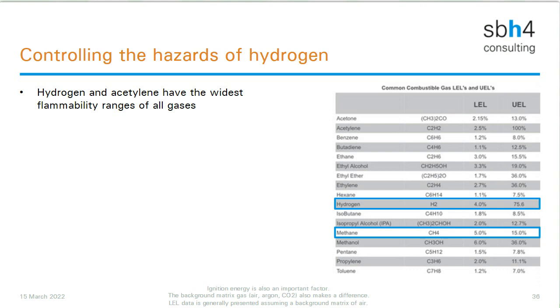Methane, you can see also highlighted on the table here, is of course flammable, and a lot of gas and flame detection equipment exists to detect methane leaks. But you can see quite clearly that the lower explosive limit of hydrogen is less than methane, and the upper explosive limit is significantly more than methane. Acetylene, you can see at the top of the table, is the only gas with a wider range. So therefore, working with hydrogen or hydrogen electrolysis means we really need to pay very, very close attention to the flammability hazards.